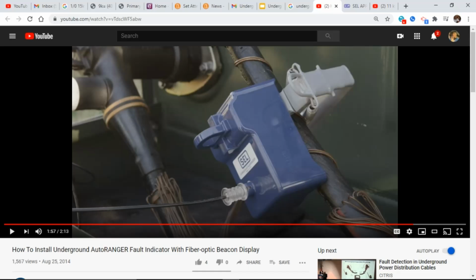Our typical practice, if you needed to have the elbow grounded up here at the top with these two strands, is to make a loop around the fault indicator and then go up to the elbow. That was our general practice. So no grounds were going to be under the indicator measurement, just the primary conductor itself. So that was our practice.